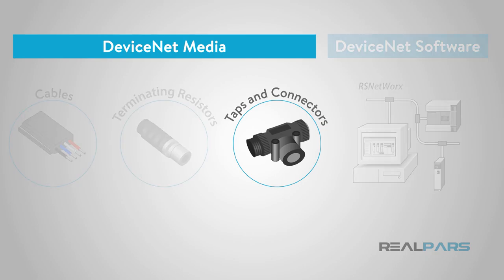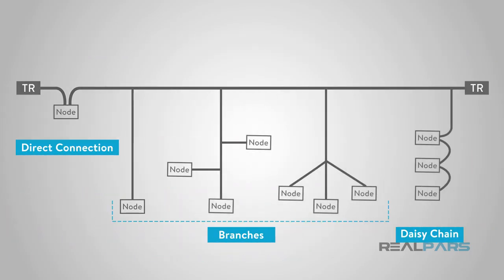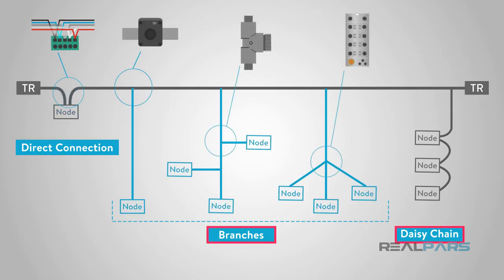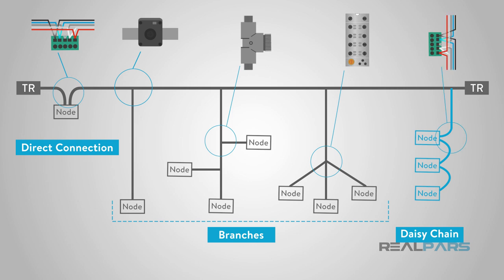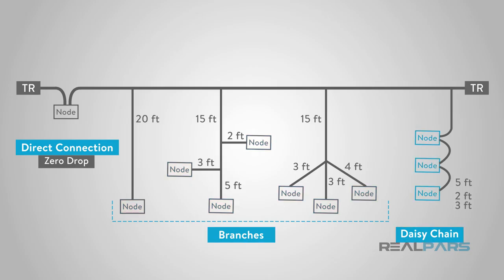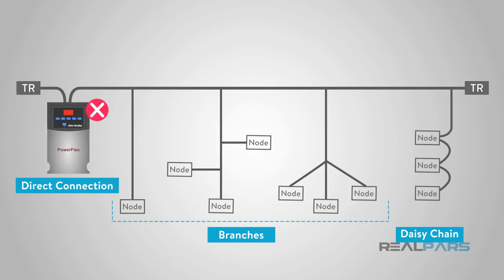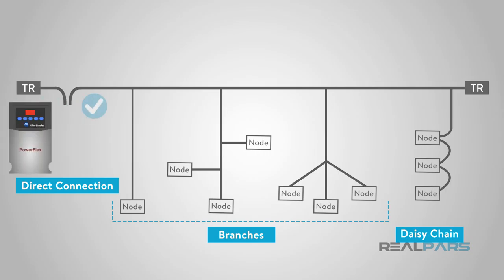You can connect the trunk line to devices using multiple types of taps and connectors. Devices can be attached either directly to the trunk line, by branching, or by daisy chaining them together. This choice impacts the total drop length calculation, as direct connections are considered zero drops while branching or daisy chaining adds to the calculation. These connections were specifically designed to allow devices to be replaced without disrupting the network.